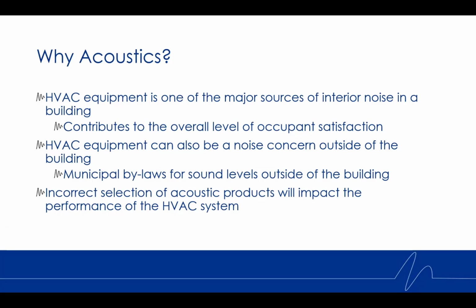And lastly, the reason this is important is we want to make sure that any sort of noise control product that we put onto a system is selected properly. They will have an impact on how the product functions, and we want to make sure that the HVAC system is designed in order to accommodate the noise control measures, and that's not going to have an overall impact on the performance of the equipment and the system.